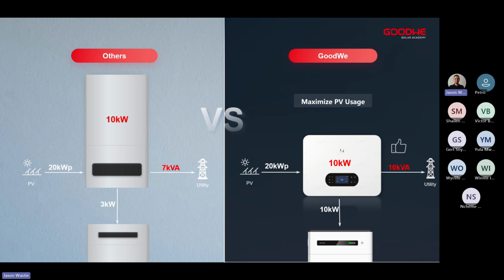We'll get 7 kilowatts or 7 kVA running to the utility, running to the loads, and the additional 3 kilowatts would go down to the inverter, to the battery to charge. There's a loss of 10 kilowatts on the system. A lot of manufacturers out there can do a degree of this, 120% or 140%, where we can use an additional 10 kilowatts of what the nameplate is.